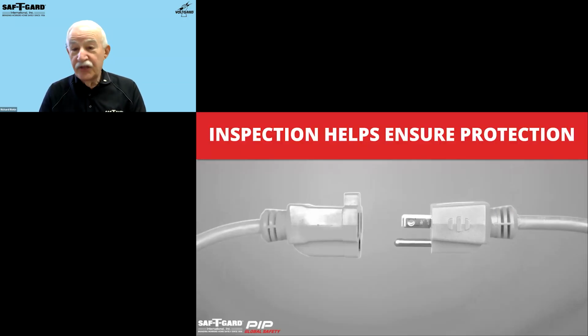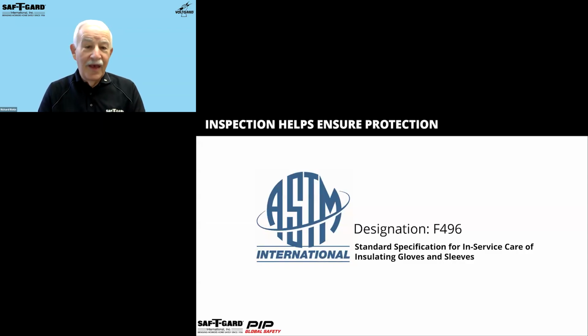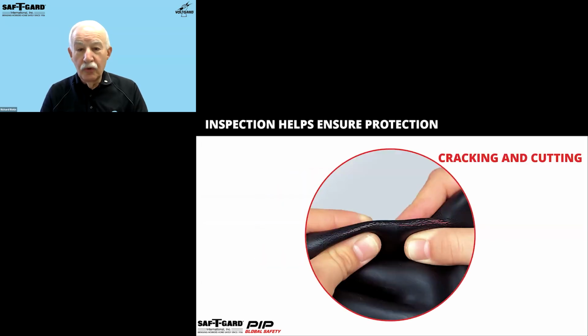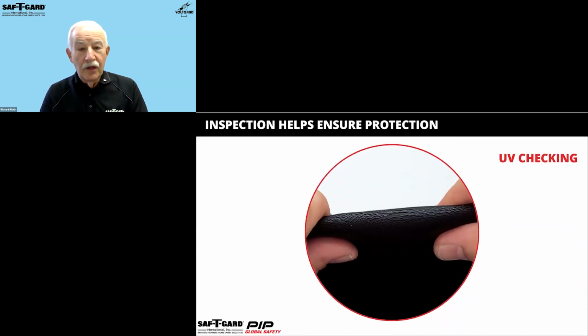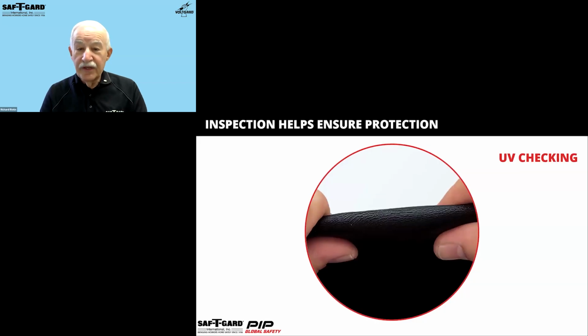Now, besides just designing the products, we have to inspect them before use. And the guide for that is another ASTM specification that is specifically referred to in OSHA, and it's the in-service standard that requires regular inspection of rubber insulating gloves. All gloves must be thoroughly inspected before use. Common problems to look for include cracking and cutting. Prolonged folding or compressing can cause this kind of rubber damage. UV checking: storing in areas exposed to prolonged sunlight causes UV checking, which also shows up as cracks in the rubber.